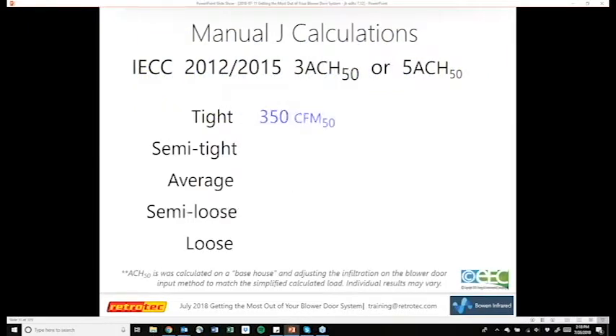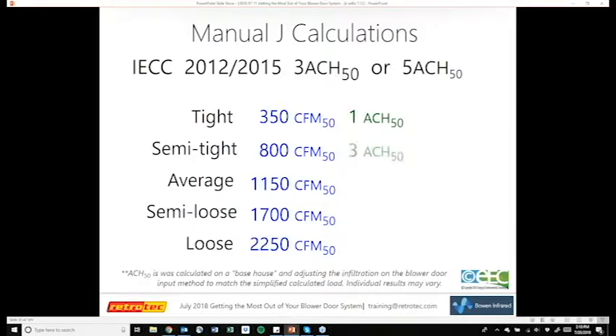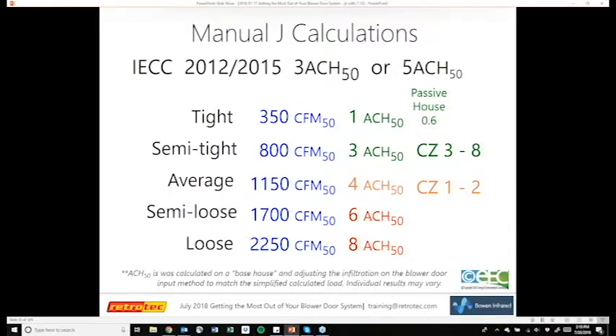And on this load calc software, you have the ability to go in and enter a blower door number. If you can enter that blower door number in, then your infiltration is going to be correct. There's no variance that's going to affect the sizing. Infiltration can be 15, sometimes 20% of the load, depending on how leaky that house is. And so when we're talking about tight, semi-tight, average, that's how these numbers relate. We're talking 4 ACH for average. I would say that's a little more on the tighter side than your average code-built home that you're going to see.